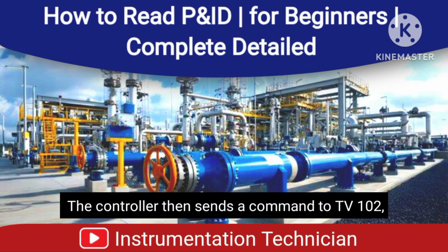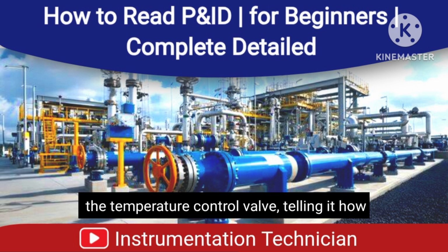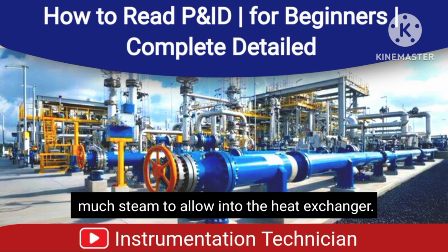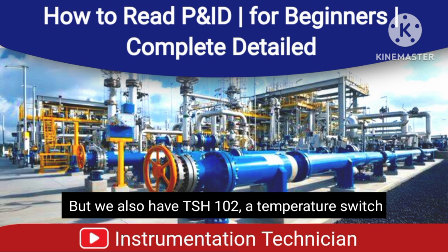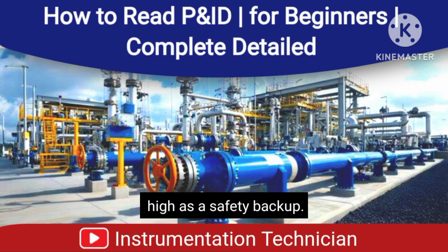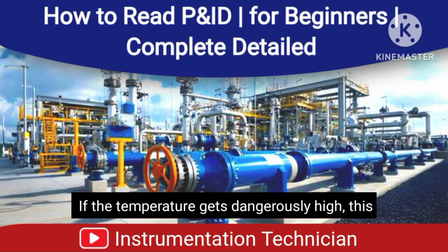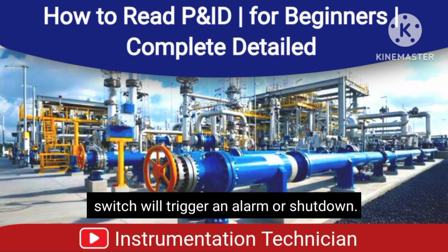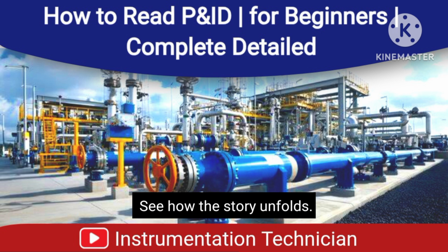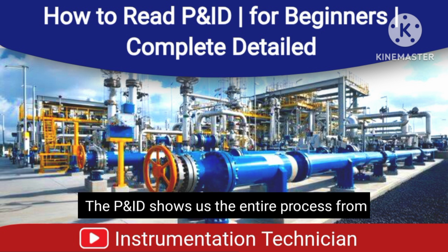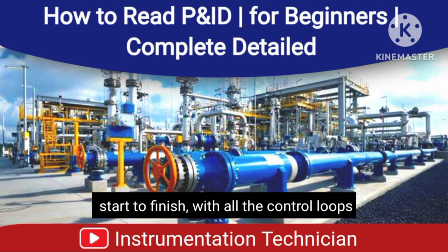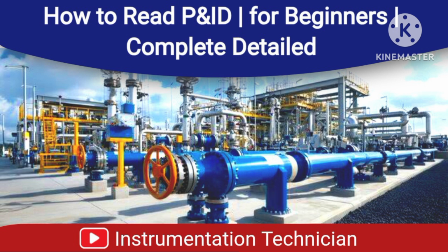The controller then sends a command to TV102, the temperature control valve, telling it how much steam to allow into the heat exchanger. But we also have TSH102, a temperature switch high, as a safety backup. If the temperature gets dangerously high, this switch will trigger an alarm or shutdown. See how the story unfolds? The P&ID shows us the entire process from start to finish, with all the control loops and safety systems.